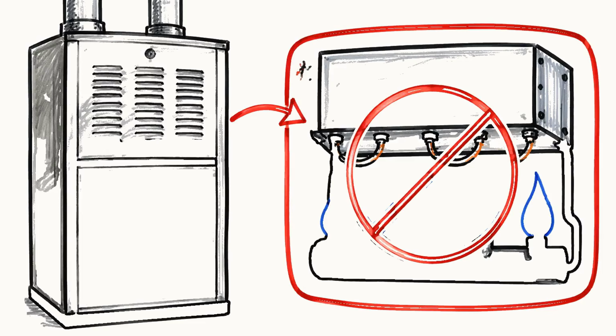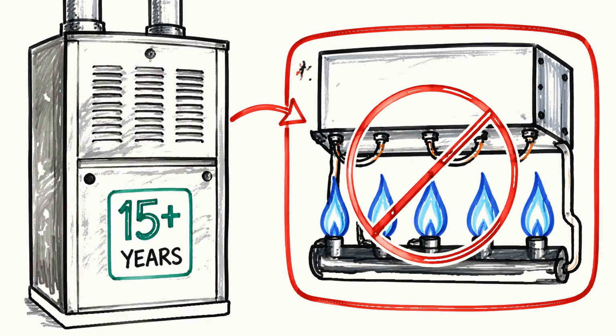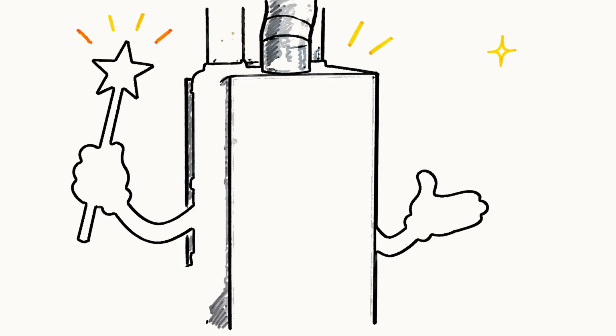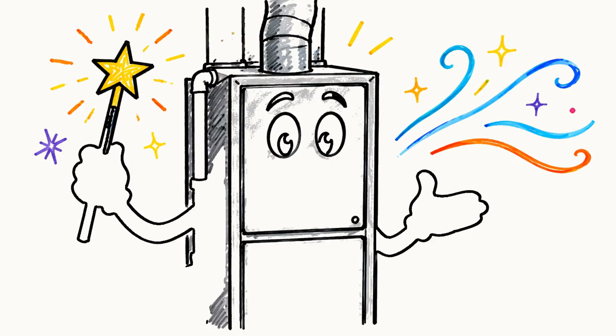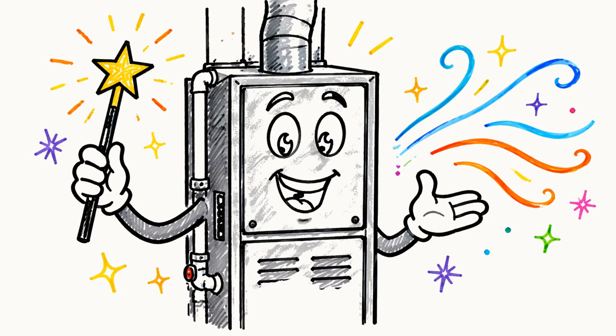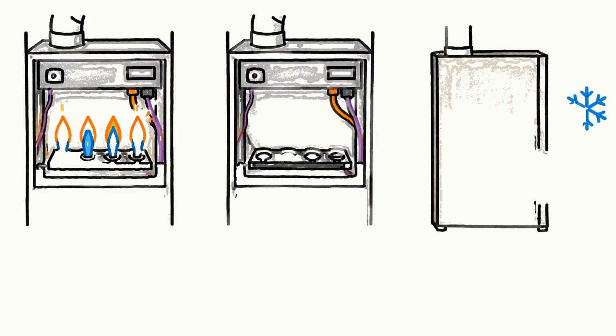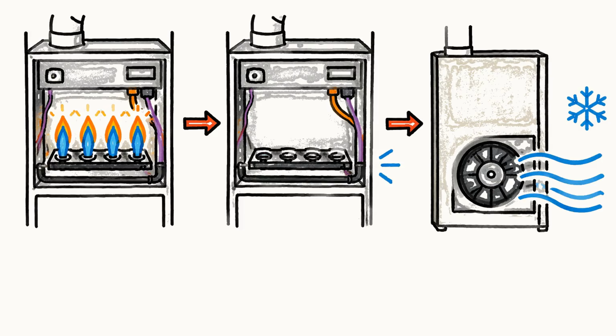Most furnaces made in the last 15 years have no pilot at all, so if yours is newer, skip this one. Now here is the one that feels like magic when it works because the furnace looks almost fine while it does it. If your burners light up, run for just a few seconds and then shut right back off while the blower keeps blowing cold.